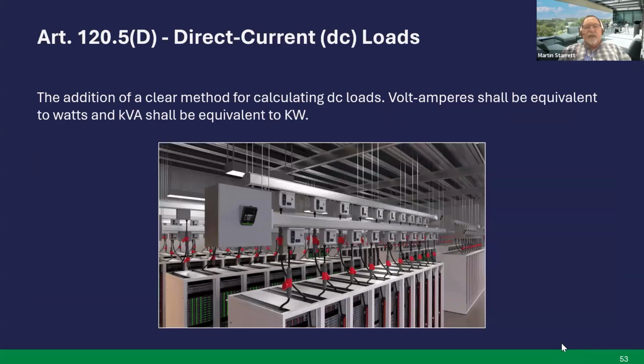Direct current loads. The addition of a clear method for calculating DC loads. Volt amp shall be equivalent to watts, and kVA shall be equivalent to kW. There's a lot more introduction of direct current in the '26 code, because we're really incorporating it back into electrical now, the DC. So you'll see a lot of added stuff in the new code. Next slide.